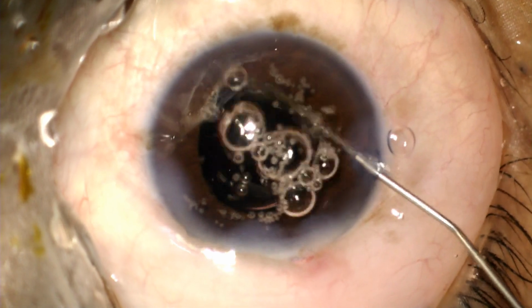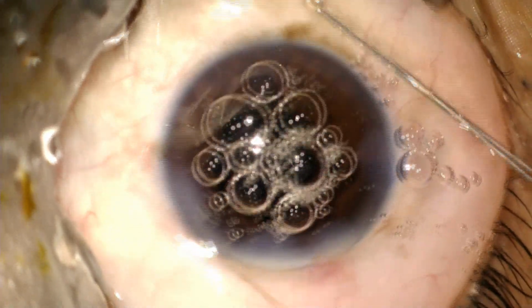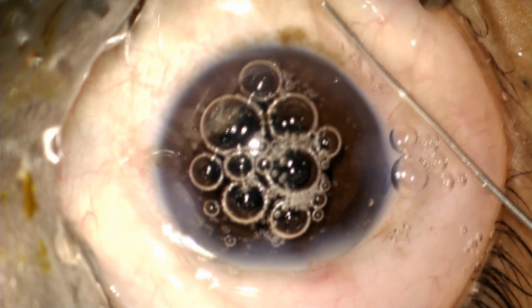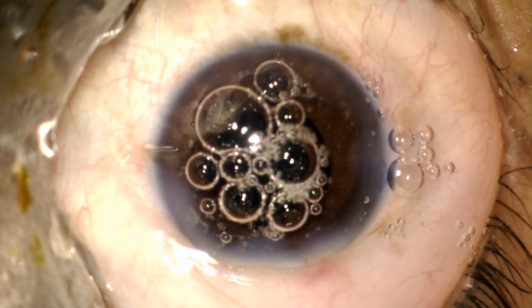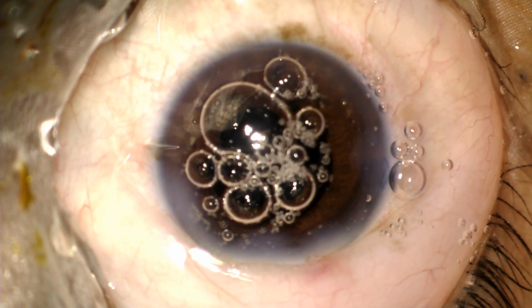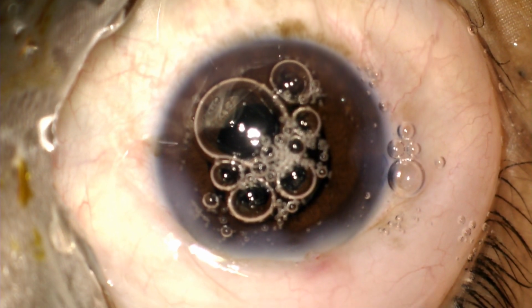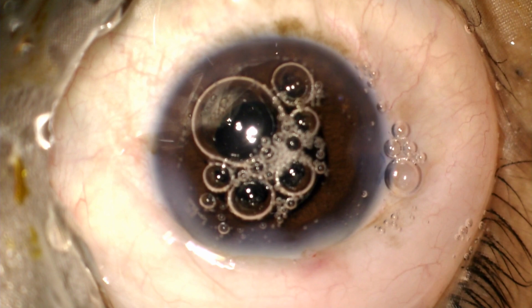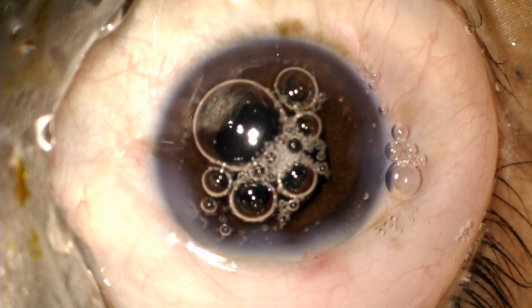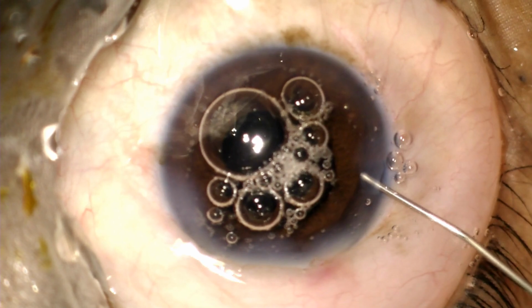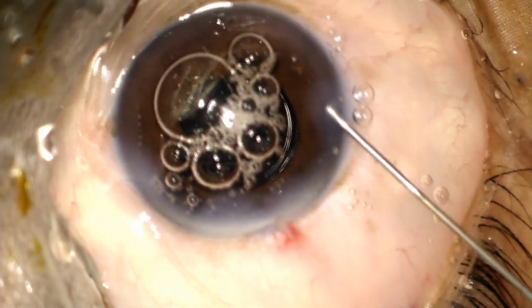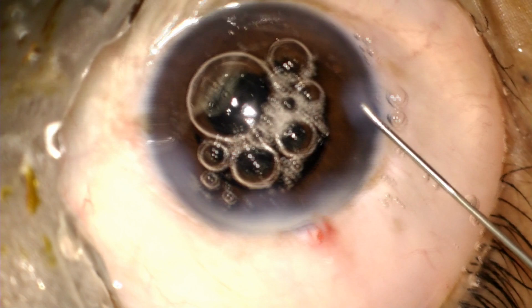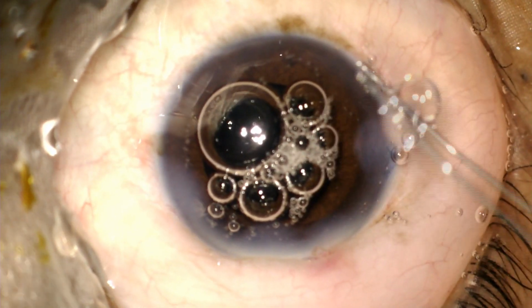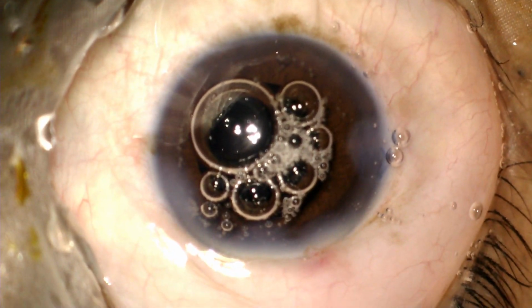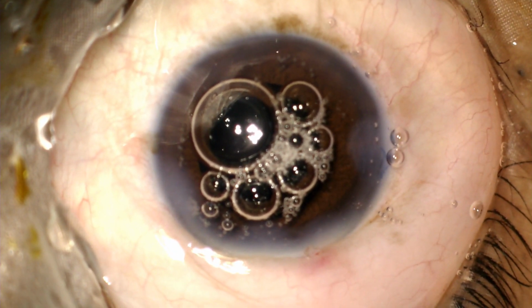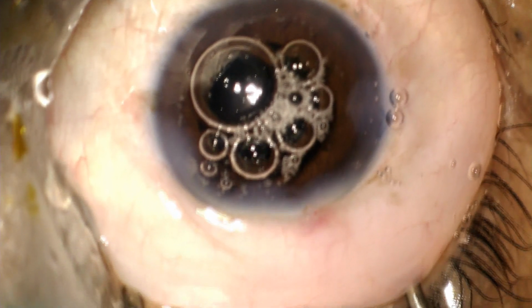But yes, I don't see a very tight chamber, so I put some air bubbles and then check the pressure again. And yeah, it looks okay to me now. The pressure is still a little less. So if the air bubble is not leaking, so it's airtight, you can get away with it. But I decide to put in a little more BSS and then hydrate the wound a bit. And then I'll check the pressure again. And now the eye is very tight. The pressure is typically around 25, around here, 25 to 30 mm of Hg.